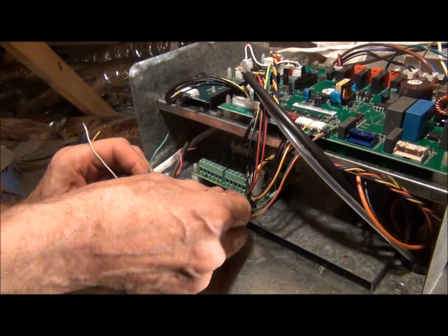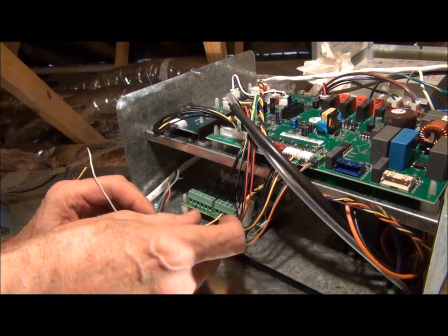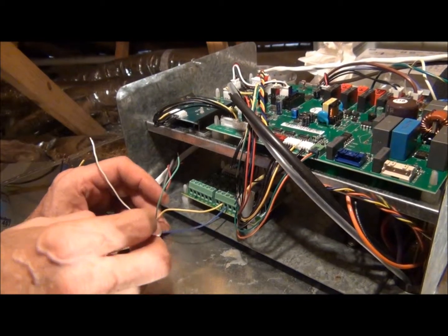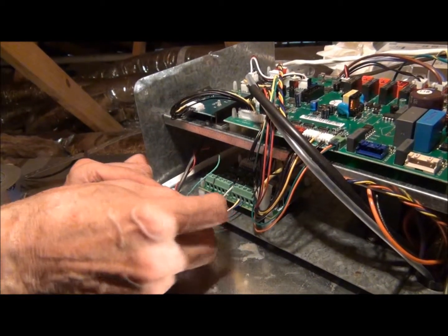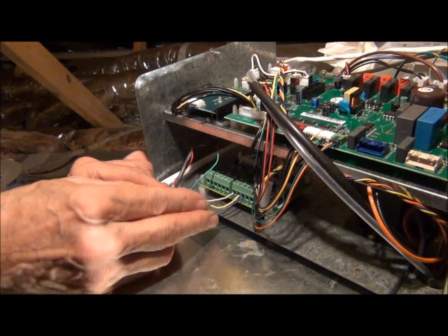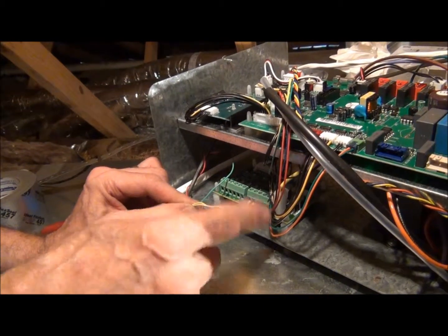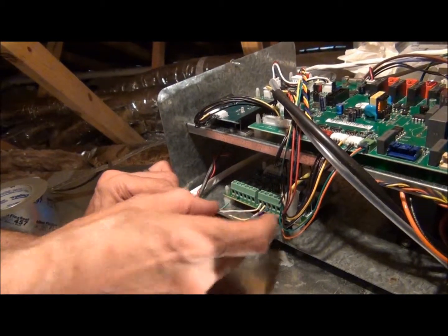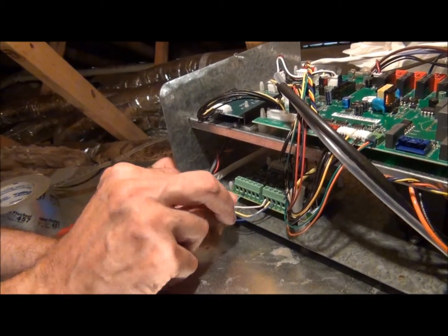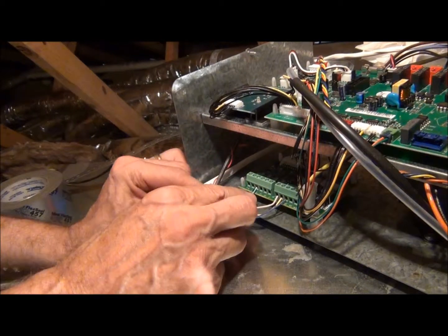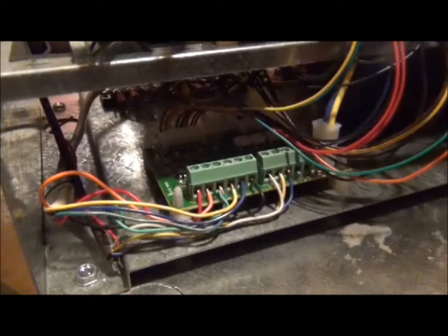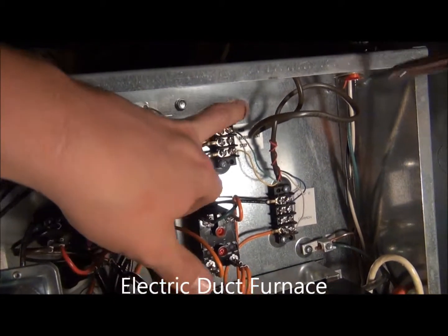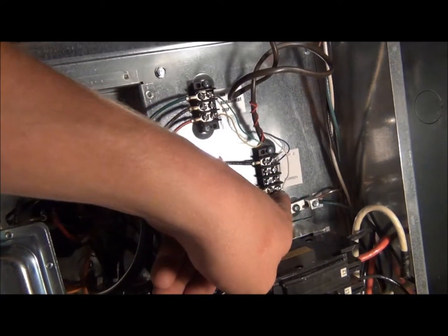We use blue for our second stage heat and yellow for our first stage. So we have W1 and W2, then we have a common. In this case we use white wire for common. We don't use W3 because we only have 10kW - W3 would be for 15kW. Then we have to hook G also with the green wire where G is on the other low voltage wires. We've got fan, stage one, stage two, and common.